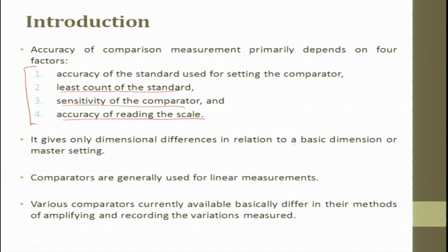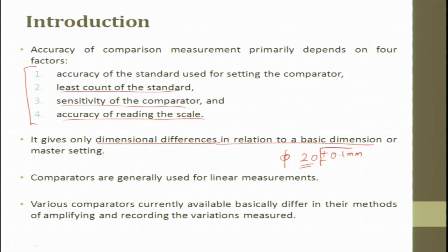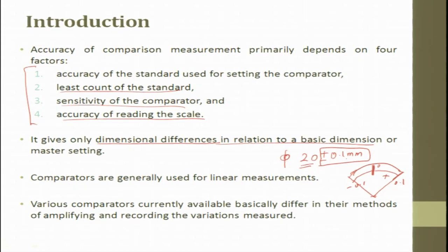A comparator gives only dimensional difference in relation to the basic dimension or master. For example, if you have 20 ±0.1 mm diameter to be measured, why always measure the 20? We measure only the tolerance deviation alone. You can have a dial gauge with a zero center, positive 0.1 on one side and negative 0.1 on the other — all you have to do is measure that deviation. It gives only the dimensional difference in relation to the basic size. Comparators are generally used for linear measurement.